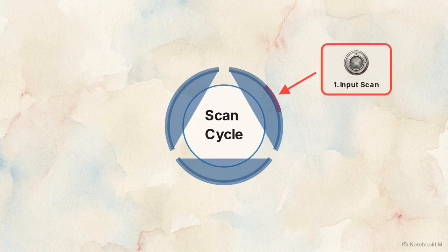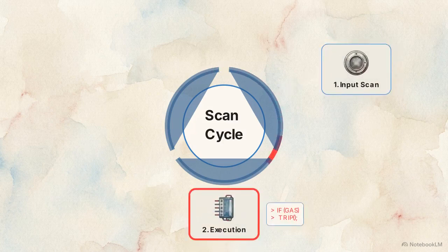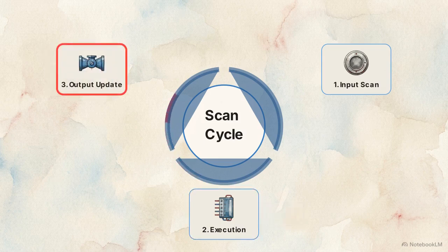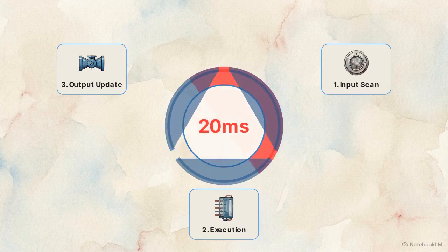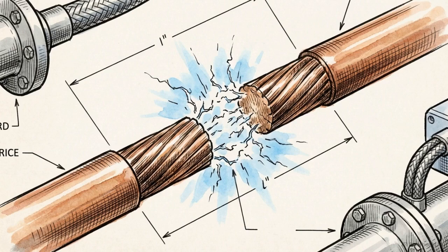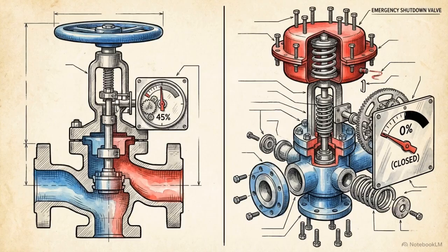First, it reads physical inputs into memory. Second, it executes the programmed ladder logic. Third, it writes the calculation to output modules. The PLC repeats this cycle every 20 milliseconds. Upon calculating a confirmed gas leak, the PLC cuts a 24-volt DC signal to the final element in the chain, an emergency shutdown valve. Process control valves modulate flow by opening partially, but emergency shutdown valves are strictly binary. They are fully open or fully closed.